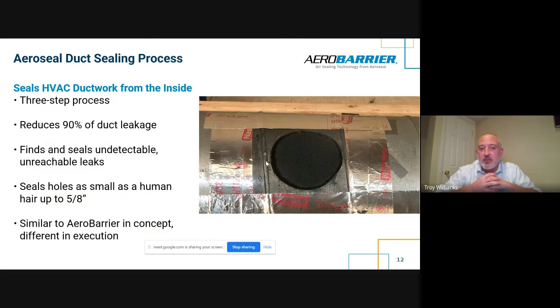Now we'll transition to Aeroseal, which focuses on the ductwork, a fantastic tool to help meet requirements for any duct blast testing you have to achieve. It works on the same principle: physics, pressurization, atomization, and airflow. It's a similar three-step process, and overall it can reduce 90% of duct leakage. It finds and seals undetectable and unreachable leaks, sealing up to a 5/8 inch hole. Pretty much the same concept, except we're talking about ductwork instead of a whole building.